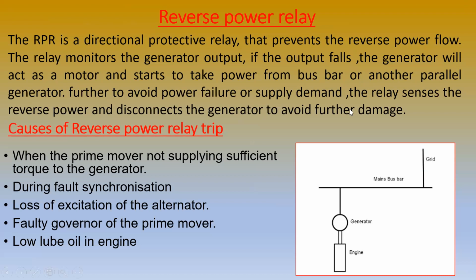See, this is an engine in the diagram. It can be a prime mover or a turbine which is connected to the generator. The generator is producing some kilowatts of power and that is connected to the main bus bar. Now, what is happening? The engine gives mechanical torque to the generator. The generator has to run with the main torque, and some losses of torque will also be there, that is friction losses, and due to magnetizing current, magnetizing torque will be there.